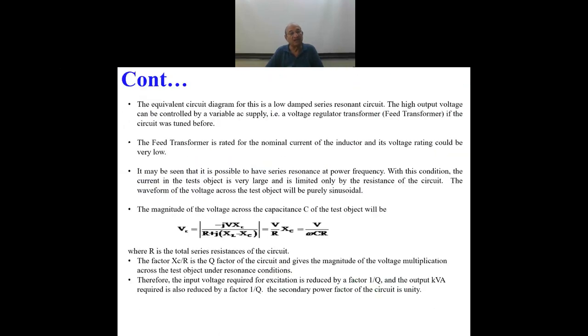We were talking about the resonance transformer for the measurement of high capacitance. We did discuss that particularly in the case of long lengths of very high voltage, 500 kV and 750 kV cables, and even if you have something like 25 or 50 meters, not too much length comes on a drum, that forms a lot of capacitance, unlike even the transformer and gas insulated system.